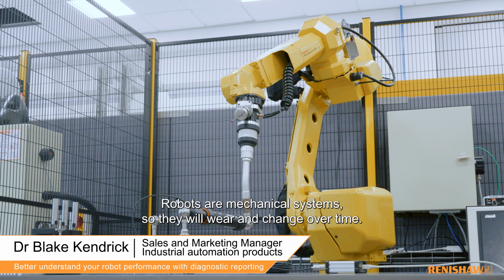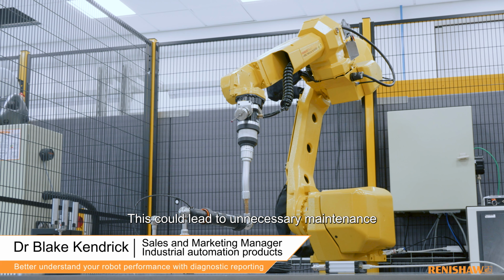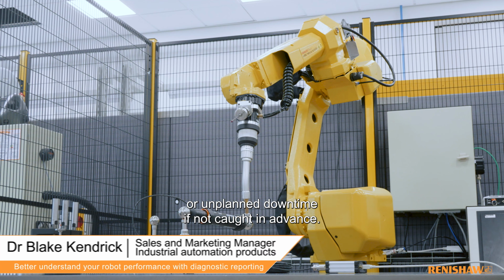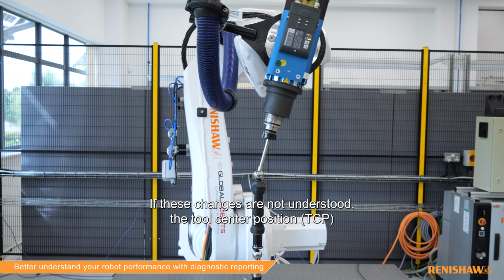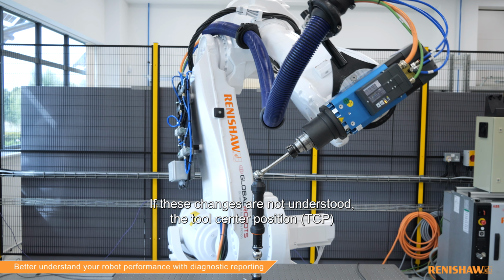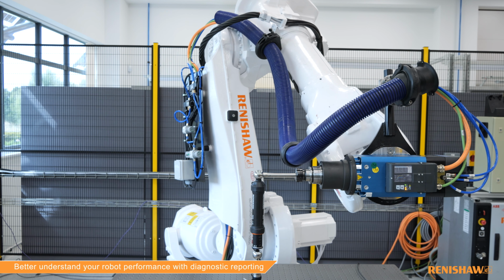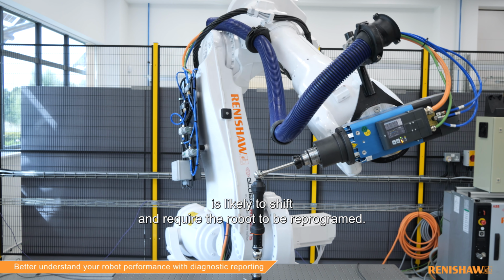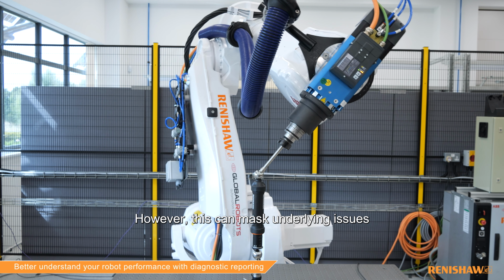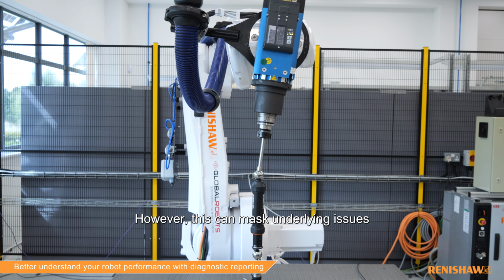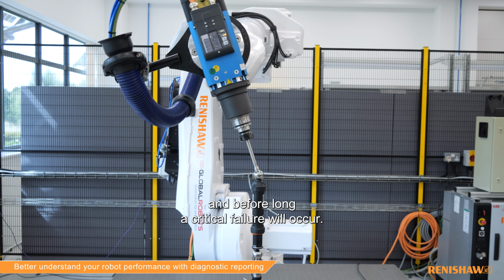Robots are mechanical systems, so they will wear and change over time. This can lead to unnecessary maintenance or unplanned downtime if not caught in advance. If these changes are not understood, the tool center position, TCP, is likely to shift and require the robot to be reprogrammed. However, this can mask underlying issues and before long a critical failure will occur.